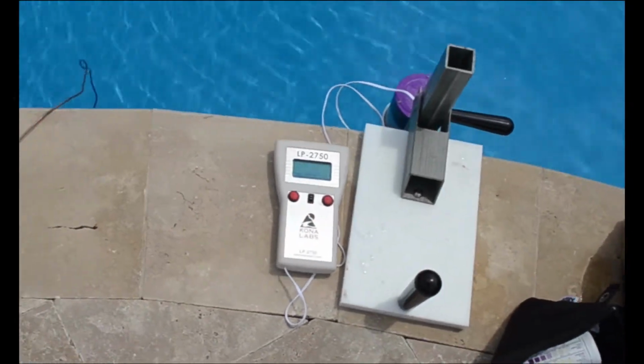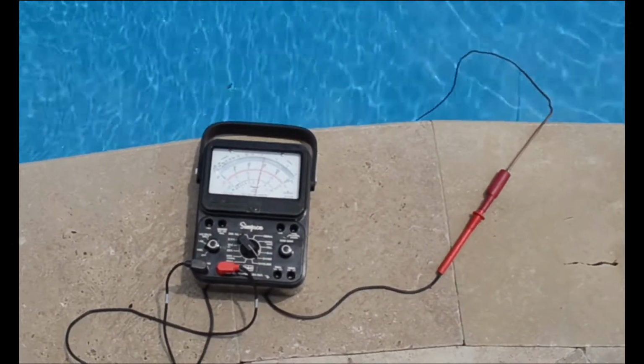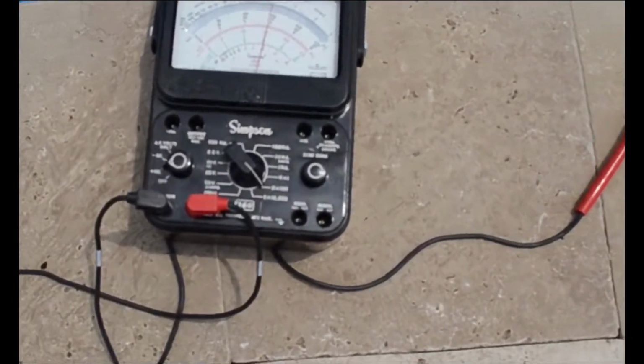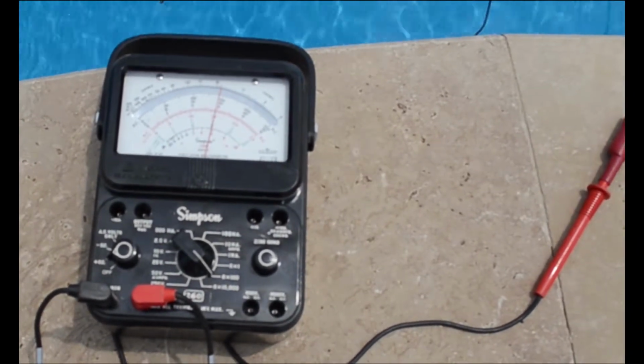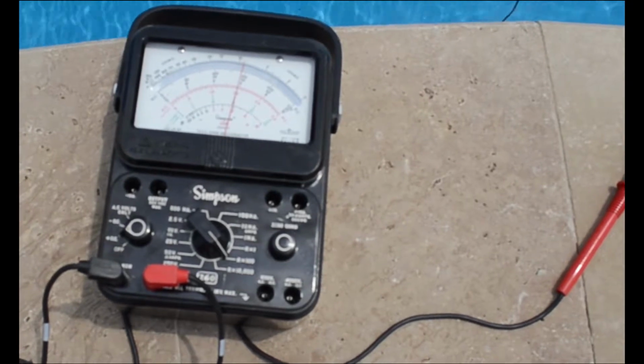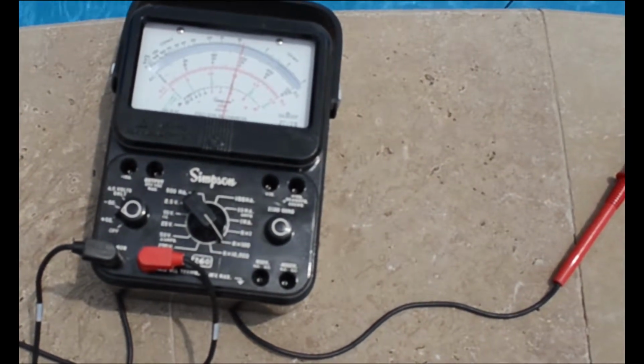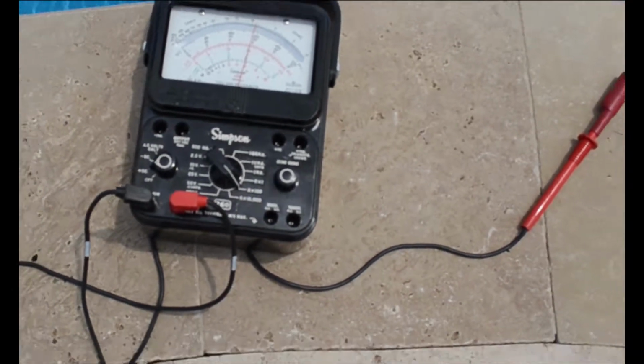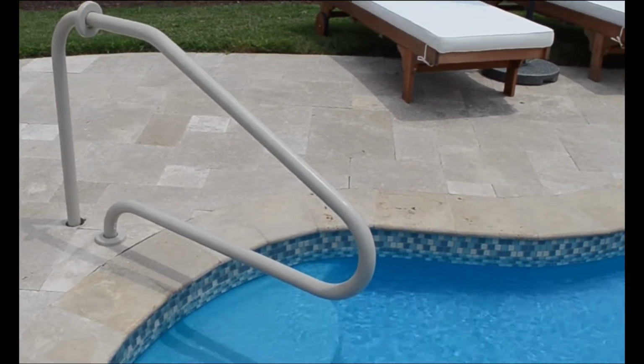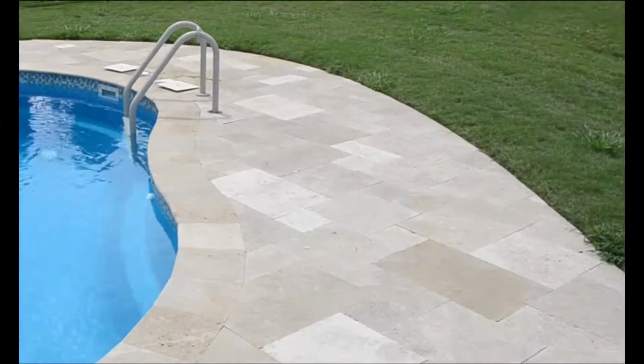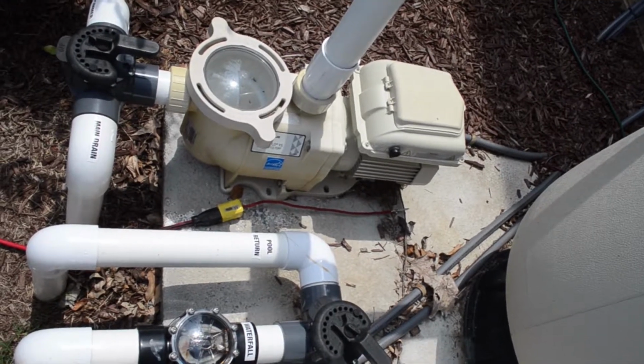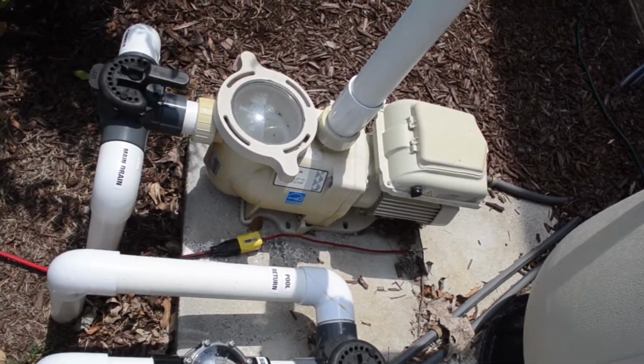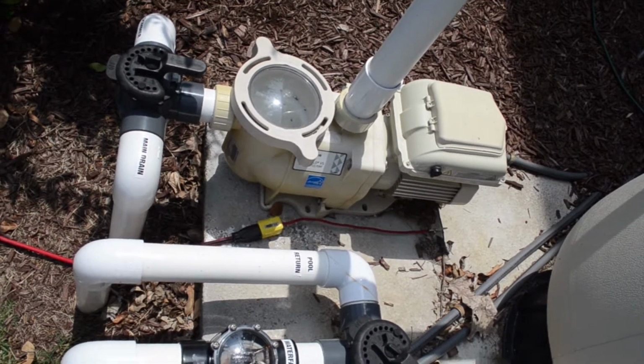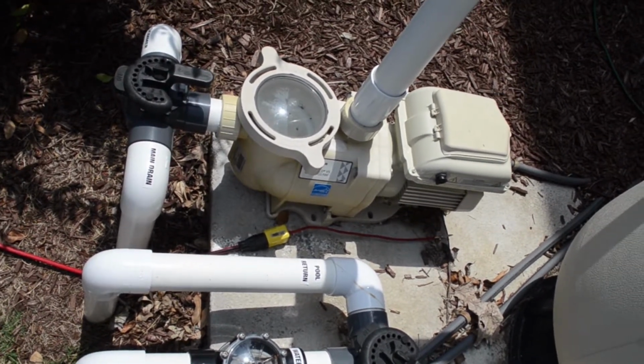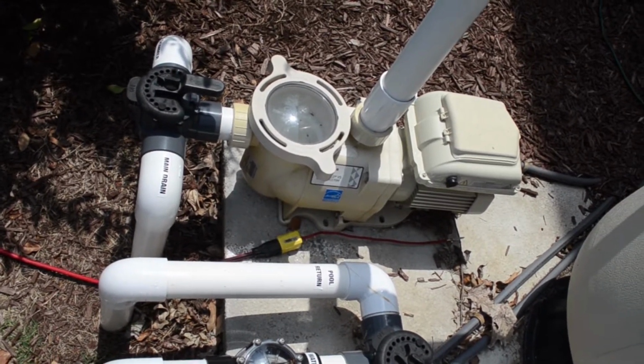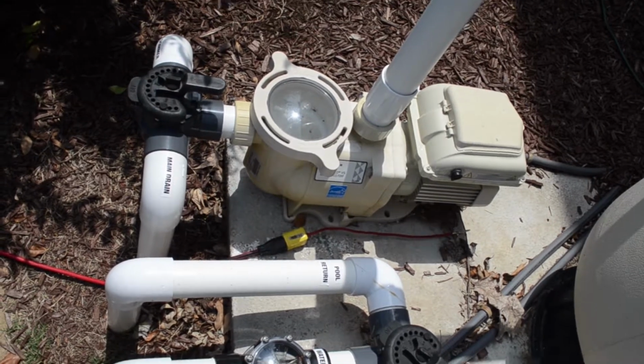Second, we're going to do a bonding check. This goes back to the bonding wire. You can see that if we just have a piece of wire in the water, we actually have conductivity back to the equipment pad where the pump is bonded, which is great. We would also check the actual railing and the handrail. You can see where the bonding wire is attached, and that bonding wire running back to the pool is connected to the pump. So that's our verification that we have connectivity between the pool, the equipment pad, and the circuit breakers, to help prevent electrocution and drowning.